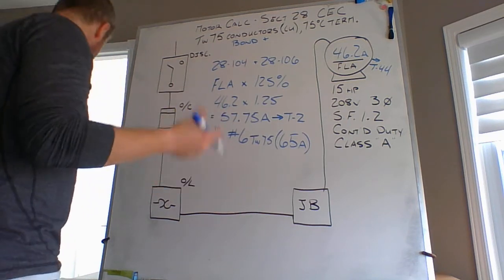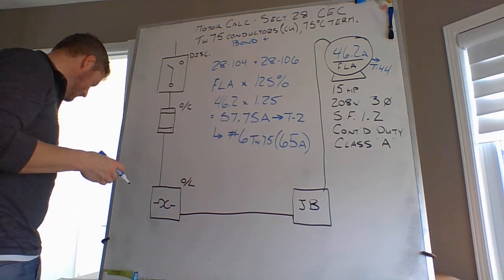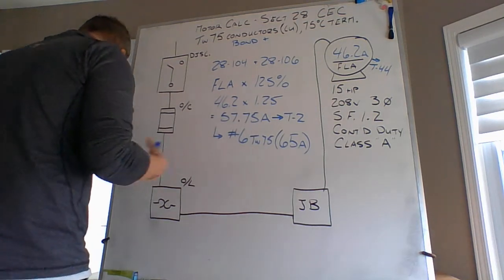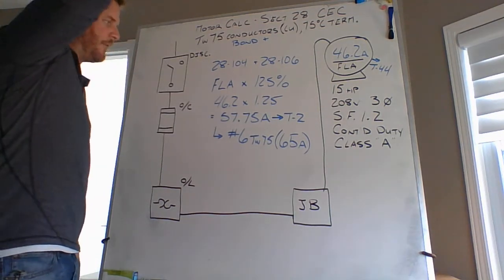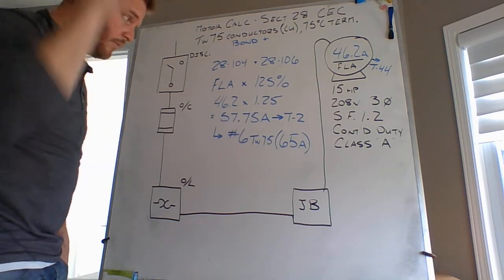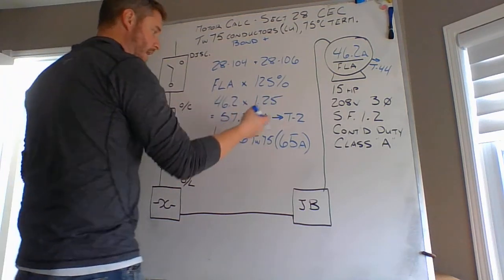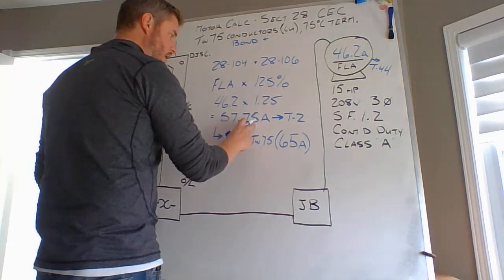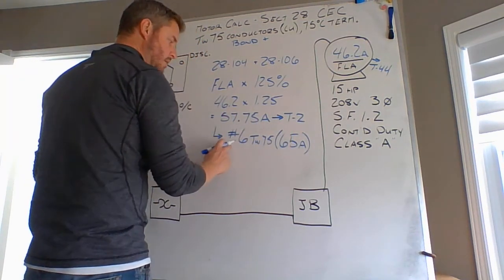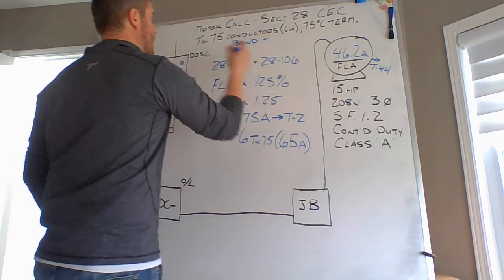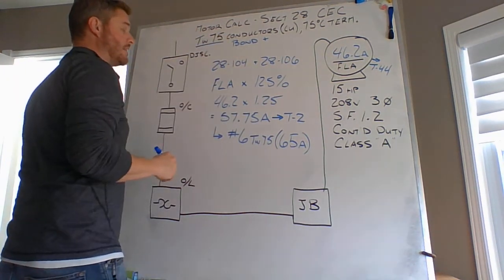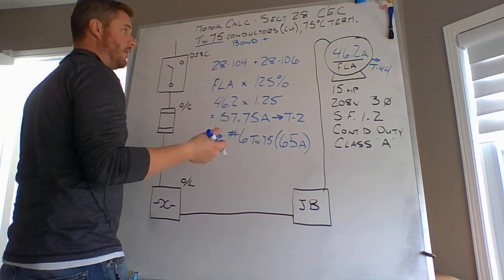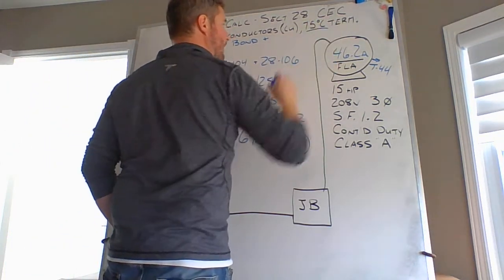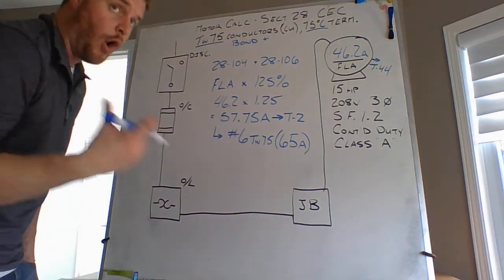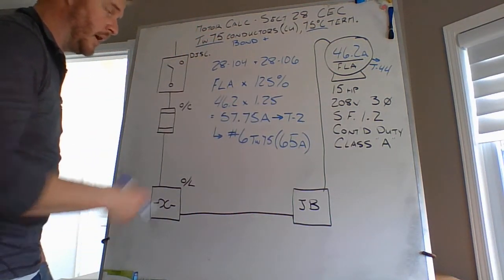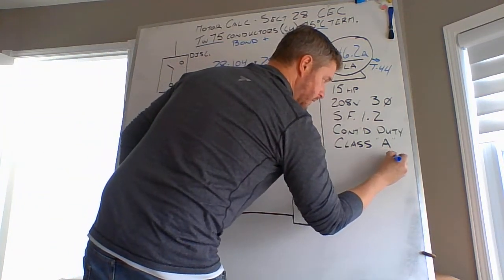This saves us a step when we're talking about voltage drop calculations. So we are looking at this conductor being 57.75 amps as a minimum, but they don't make a 57.75 amp conductor. So I take that value and I go to Table 2 and I select a number 6 TW75 conductor, because I know that my conductor's insulation rating is 75 degrees Celsius, and I have a 75 degrees Celsius termination temperature on all of my components. And that satisfies the Class A thing.